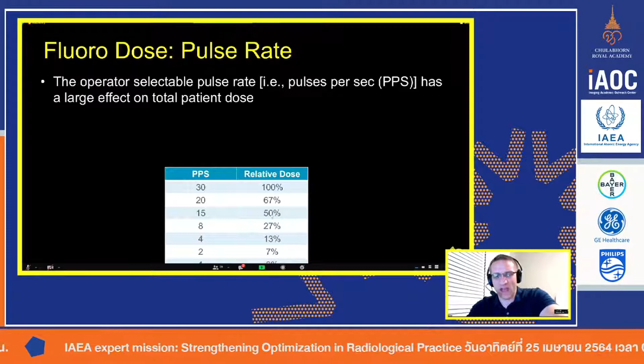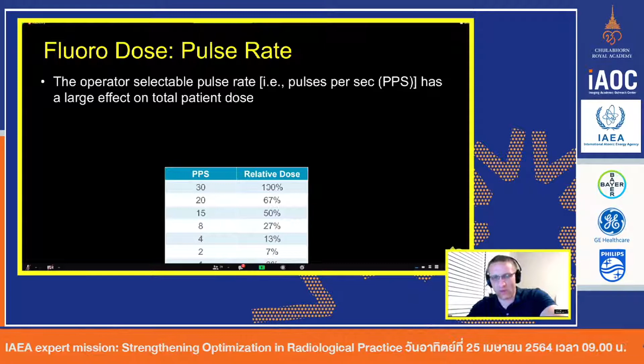If you go down to 20, you've reduced it to 67%. Obviously, if you go from 30 to 15, you've halved the dose to the patient. And then you go down to 8, 4, 2, 1. You see how the doses are dropping. If you're able to do a procedure using 1 pulse per second, you're using only 3% of the dose compared to if you had done the same procedure with 30 pulses per second. So obviously reducing it as much as feasible allows your system to reduce the dose to the patient. So it's just a quote unquote lower patient dose system.